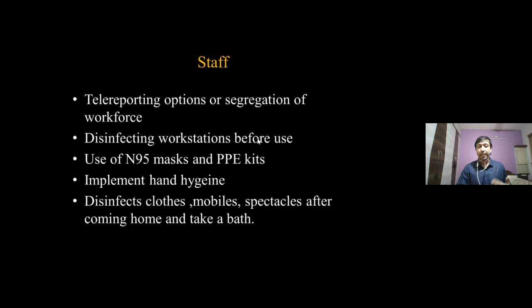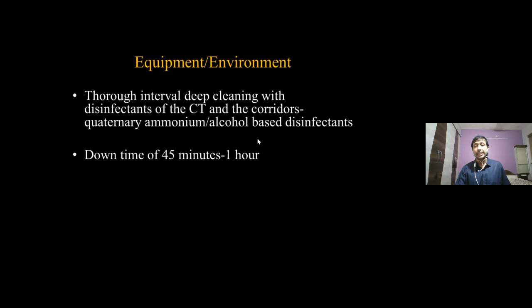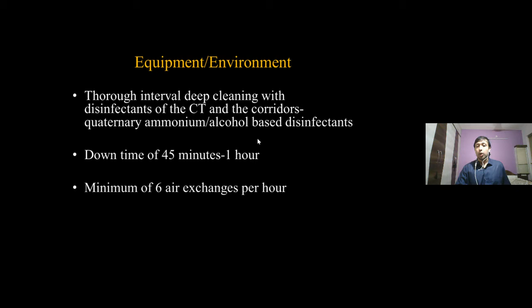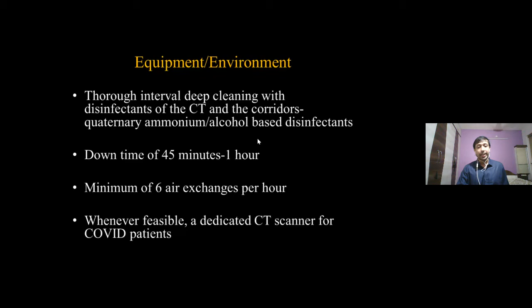At the level of the equipment, thorough interval deep cleaning with disinfectants of the CT machine, at least the gantry, and the corridors should be done with quaternary ammonium and alcohol-based disinfectants. A minimum downtime of 45 minutes to 1 hour is advisable after we do a CT of a positive patient. And a minimum of 6 air exchanges per hour are advisable to provide good ventilation. Whenever feasible, especially in a big hospital setup, a dedicated scanner should be kept for COVID patients.